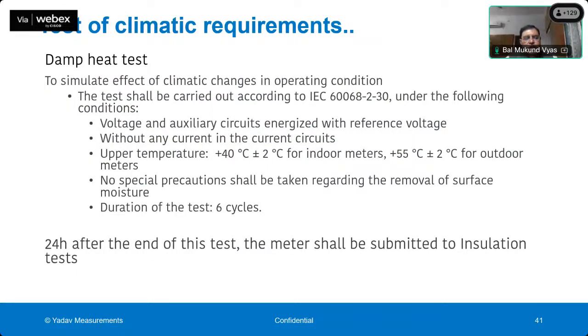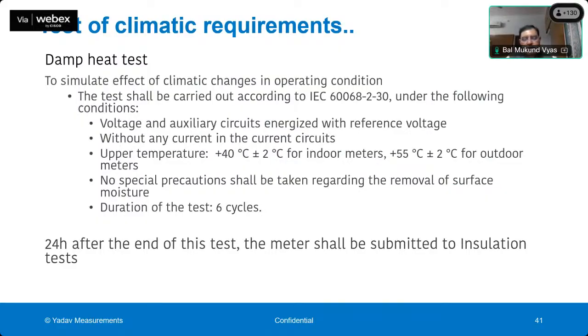Another test for the climatic requirement is the damp heat test. In the damp heat test, the meter is in normal operating condition with voltage applied but no current applied, and it is subjected to high temperature and high humidity. The upper temperature for an indoor meter is 40 degrees centigrade. For an outdoor meter, it is normally 55 degrees centigrade, with a humidity cycle. The humidity is kept at somewhere around 93%, plus or minus 3%, and it is varied between the cycle. This test goes on for 6 days in an environmental chamber.